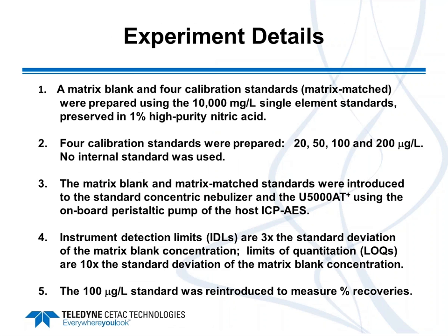So, experimental details: we prepared a matrix blank and 4 calibration standards which were matrix matched for the very hard water matrix. For the standards we used 20, 50, 100, and 200 parts per billion of a multi-element standard including uranium. For this experiment we used no internal standard.